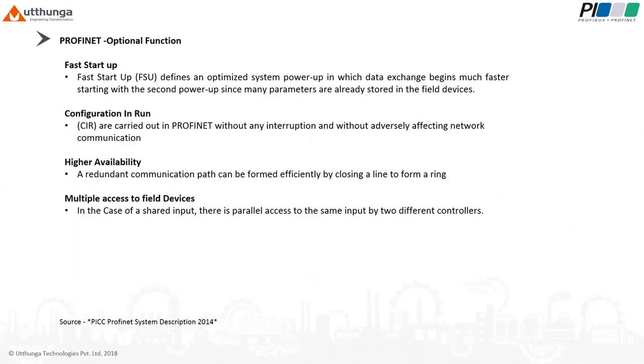Then PROFINET optional functions. Fast startup. Fast startup defines an optimized system power-up in which data exchange begins much faster, starting with the second power-up, since many parameters are already stored in the field devices. This optional path can be used in parallel with standard power-up.